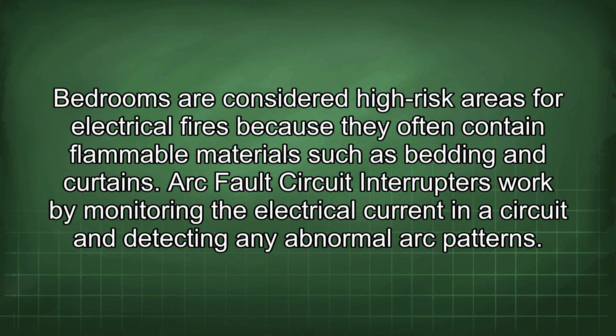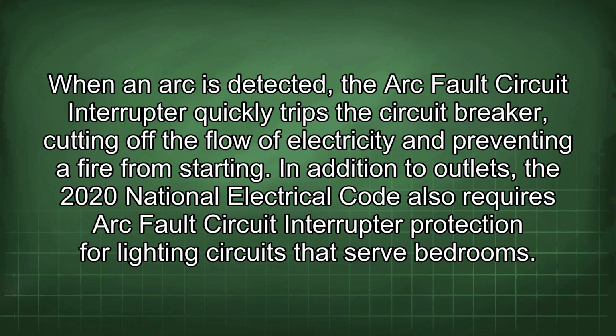Arc fault circuit interrupters work by monitoring the electrical current in a circuit and detecting any abnormal arc patterns. When an arc is detected, the arc fault circuit interrupter quickly trips the circuit breaker, cutting off the flow of electricity and preventing a fire from starting.